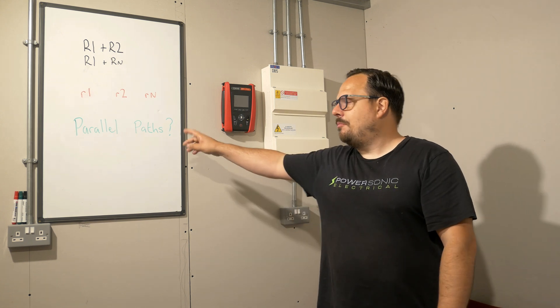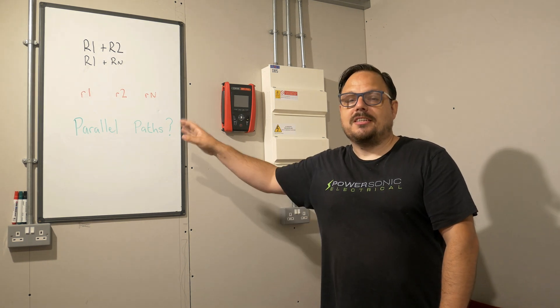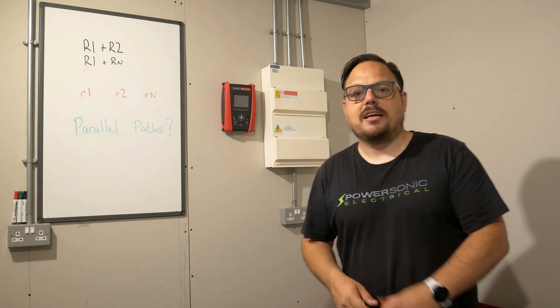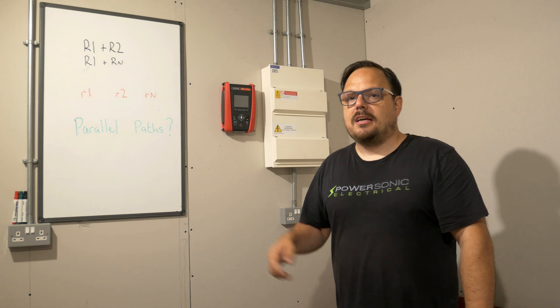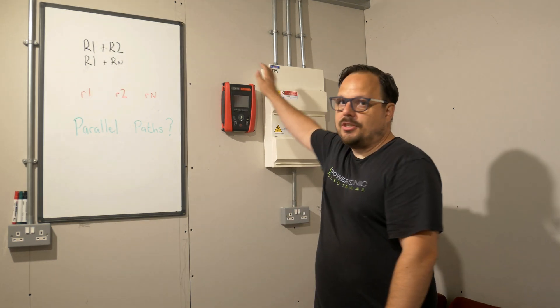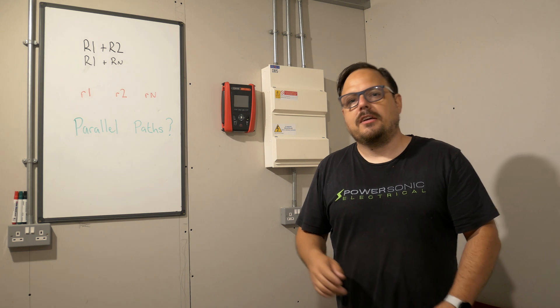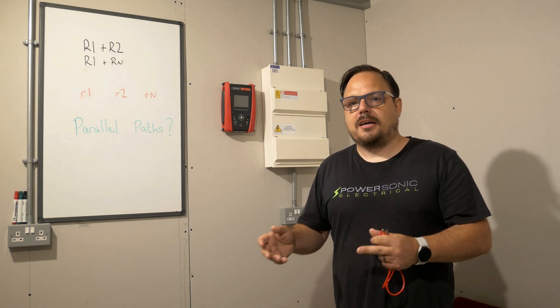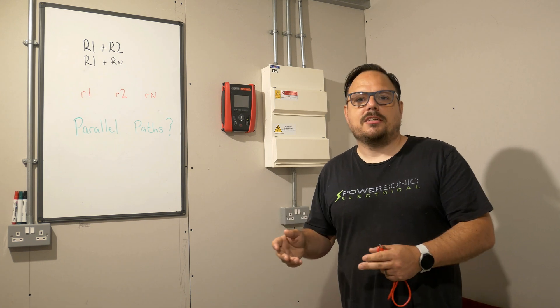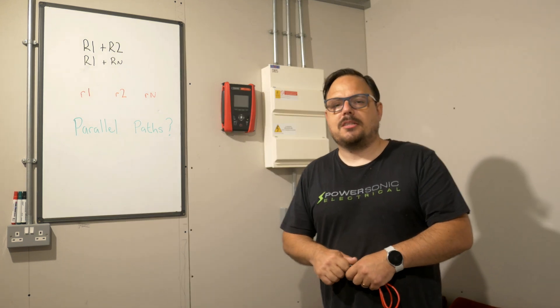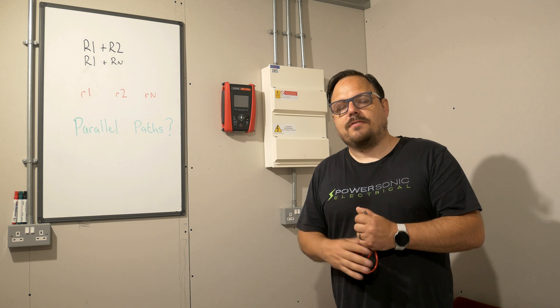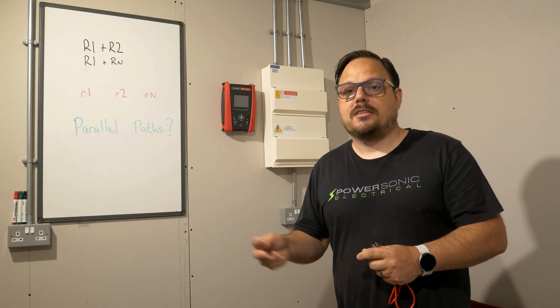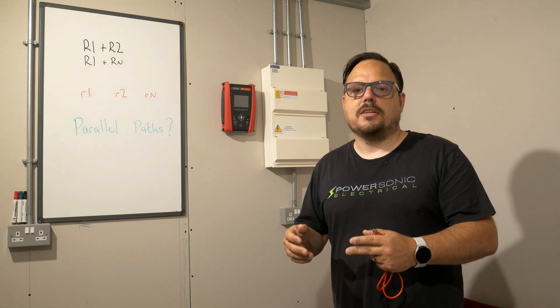You can see I've put a big note on the board that says 'parallel paths'. These sockets are metal clad in metal conduit and that conduit terminates into the distribution board behind me. So you are never going to be able to remove all of the earth parallel paths within an installation when metallic containment is in use. It is very difficult, so you need to be aware as the person carrying out the test how that can impact on your results.